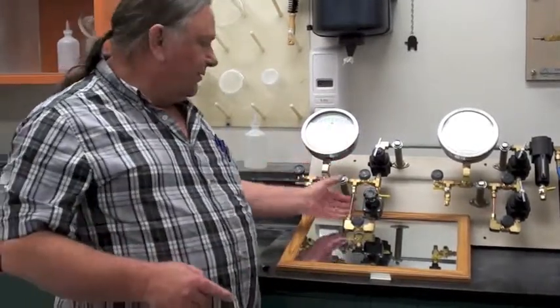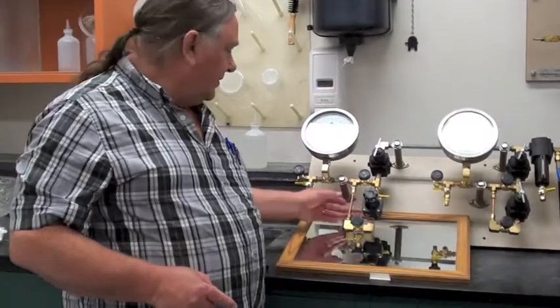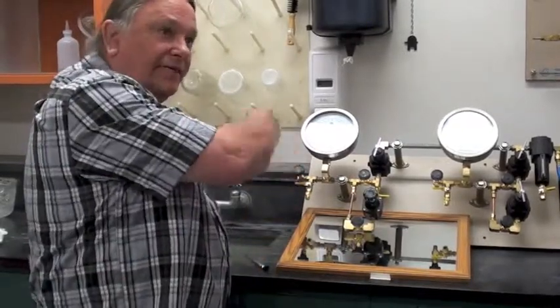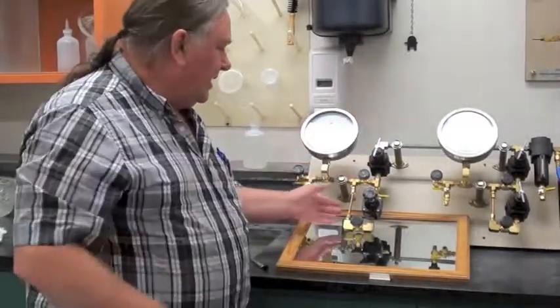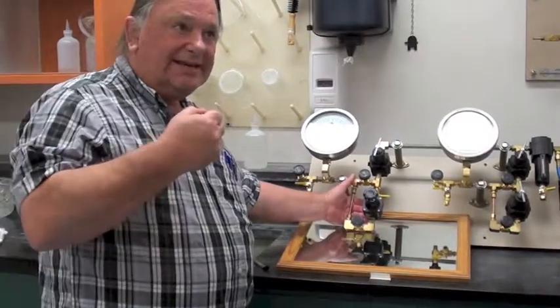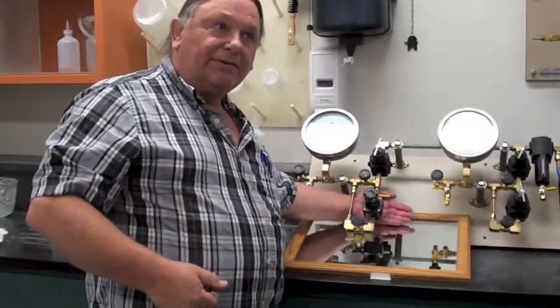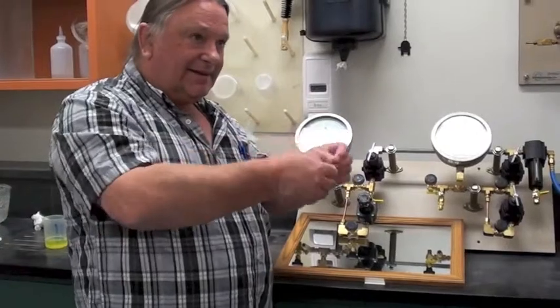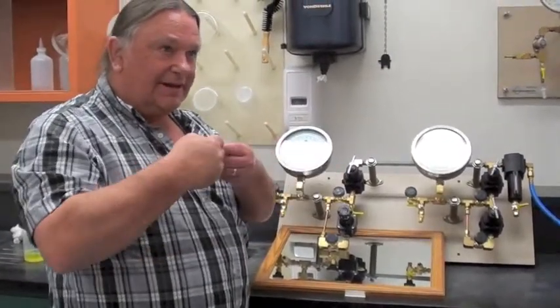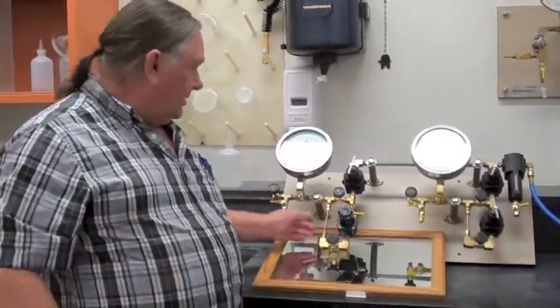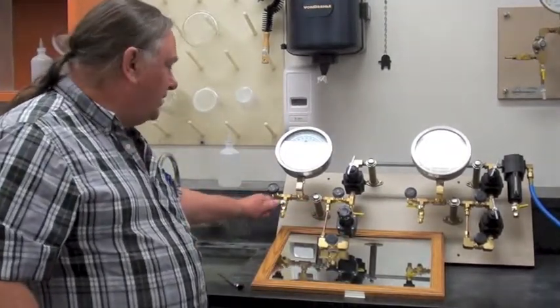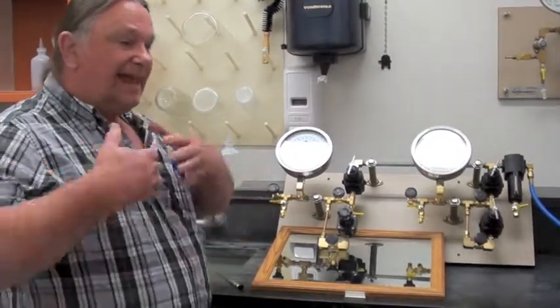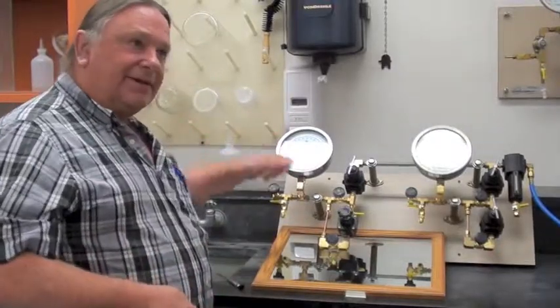There's one other way where you can run into a problem with this pneumatic. And what's called is ram pressure. I'm going to leave these off because I don't want to do it. But if you do very quick, off, on air pressure ramps in the back of the pneumatic, there's a seat that will actually come out. And then the high pressure air will be happening all the time. You can fix that by taking off the brass, removing the plastic pieces, and pressing the feet back in, and then replacing the pieces. But never random air pressure, never quick, always slow. Slow is okay. Very quick can cause trouble. It's like a hammer. Very quick air pressure is like hitting this thing with a hammer.